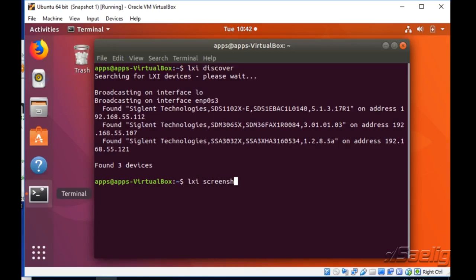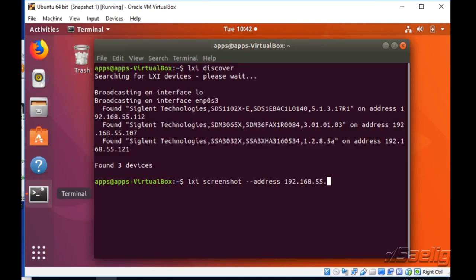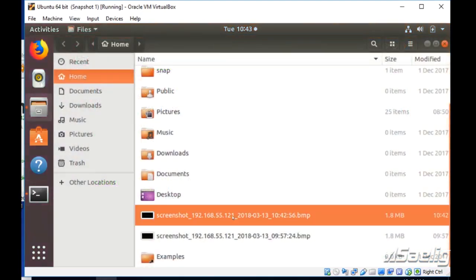We can also do a screenshot, which is just LXI space screenshot and then the IP address for the instrument. I'm going to type in the address to the analyzer and that's going to quickly give us a screenshot of the analyzer. Now it's been saved to the hard drive here.